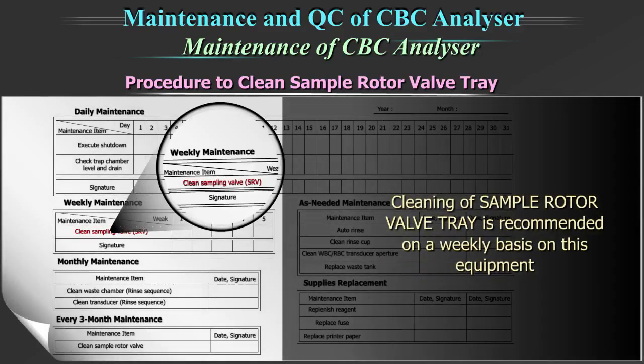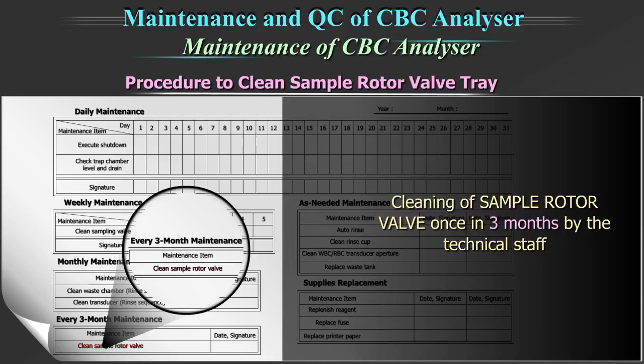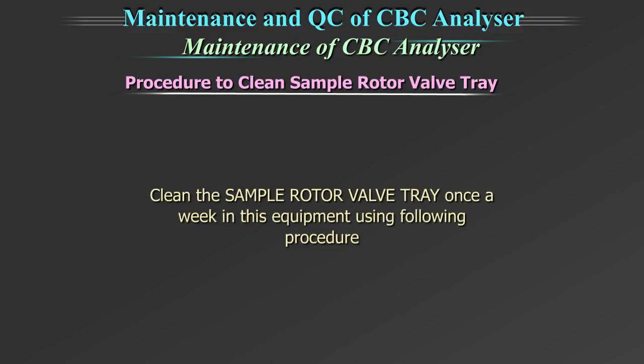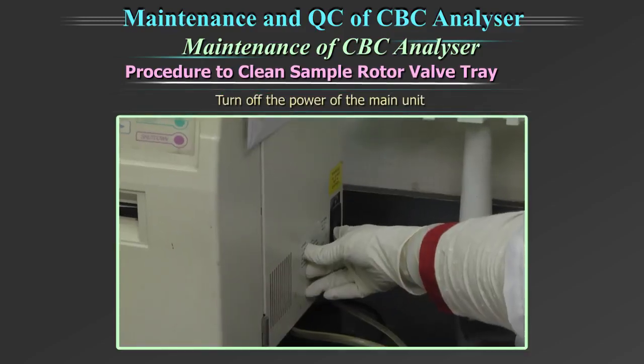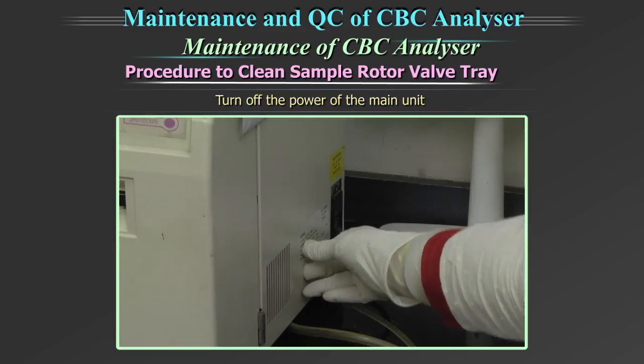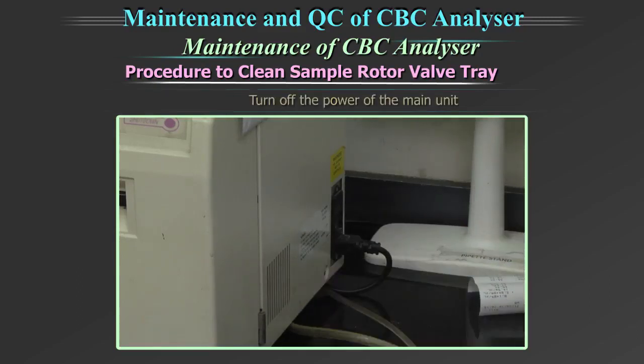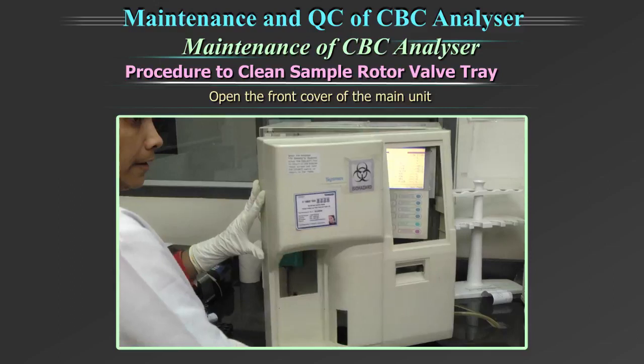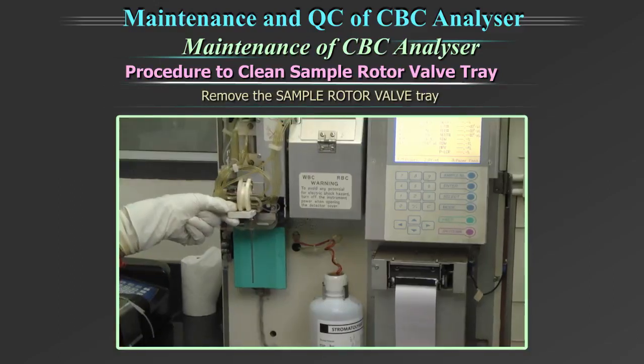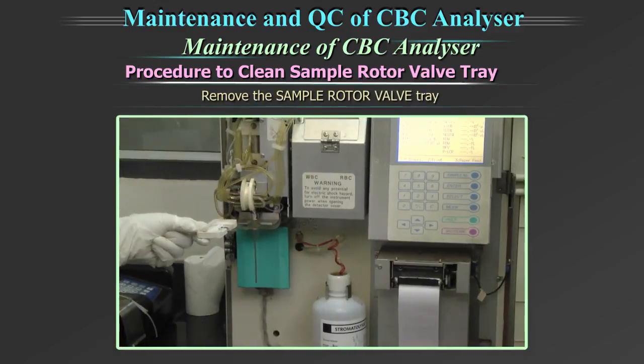Cleaning of sample rotor valve tray is recommended on a weekly basis on this equipment. Cleaning of sample rotor valve is done once in 3 months by the technical staff. Clean the sample rotor valve tray once a week in this equipment using the following procedure. Turn off the power of the main unit and wait approximately 30 seconds. Open the front cover of the main unit. Remove the sample rotor valve tray.